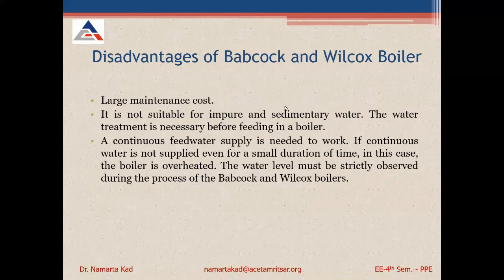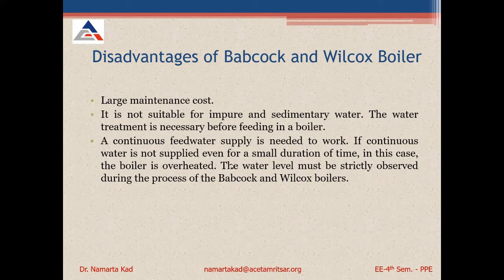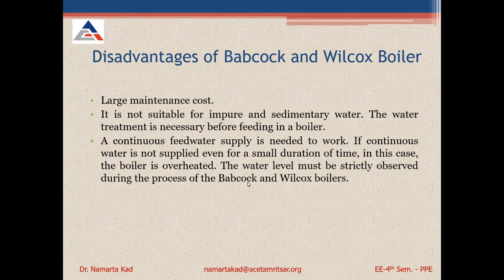Disadvantages of the Babcock Wilcox boiler include large maintenance cost and unsuitability for impure or sedimentary water — water treatment is necessary before feeding. A continuous feed water supply is required; if continuous water is not supplied even for a short duration, the boiler overheats. The water level must be strictly monitored during operation.